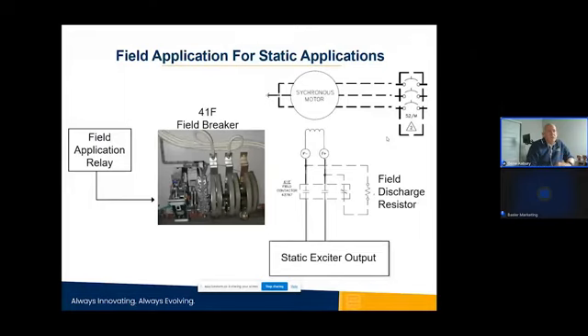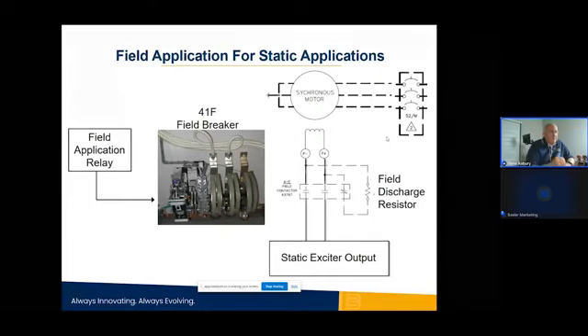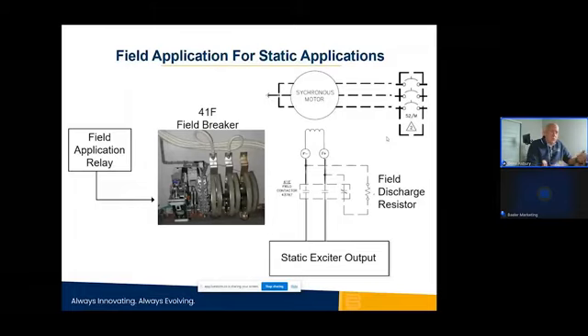With synchronous motors, you can run at a unity power factor, or you can run at a slightly leading power factor. So now you're generating magnetizing current out to the system. And if this is in a big industrial plant, this will create improved power factor, much like a capacitor bank would do.